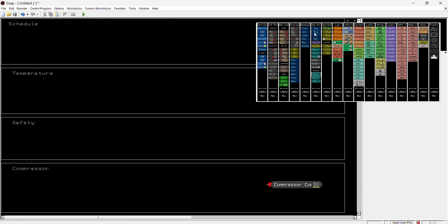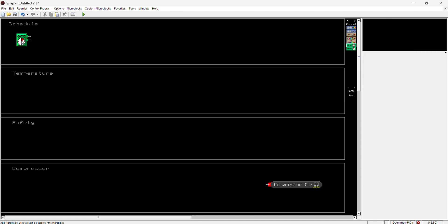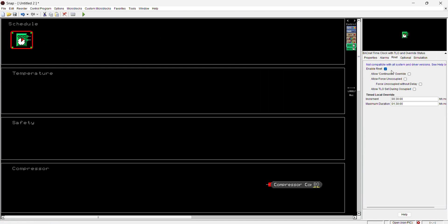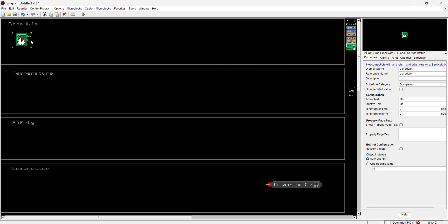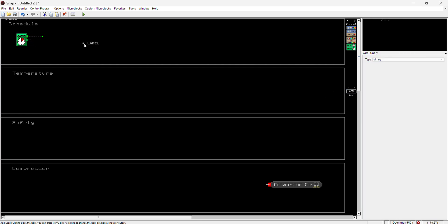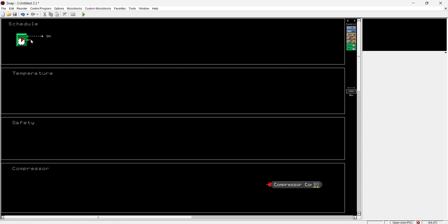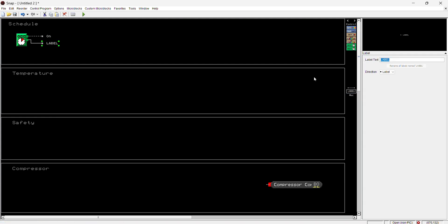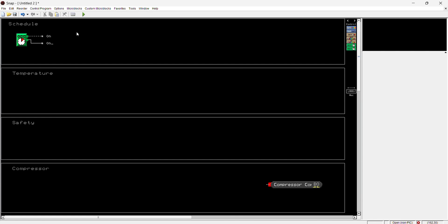Let's work our way down and put in a schedule block. A lot of controllers, even some commercial thermostats, let you set a schedule where you want the system to turn on — for example, Monday through Friday from 8 to 5 PM. That means if it's Monday at 6 PM it won't turn on because it's past 5 PM, so it sends an OFF signal. For now I'm just going to put an ON signal so you can see how it works with the schedule block.